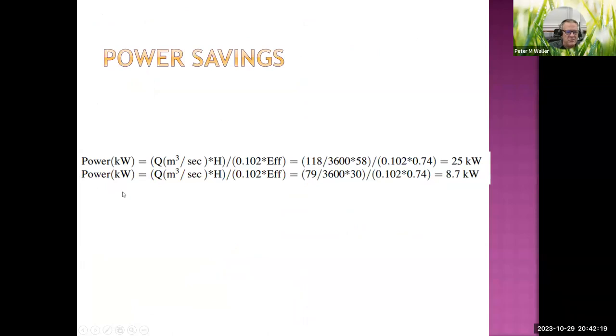The key benefit of variable speed pumps: power drops from 25 kilowatts to 8.7 kilowatts — a dramatic reduction. Variable speed pumps are more expensive upfront but can save a lot of energy.